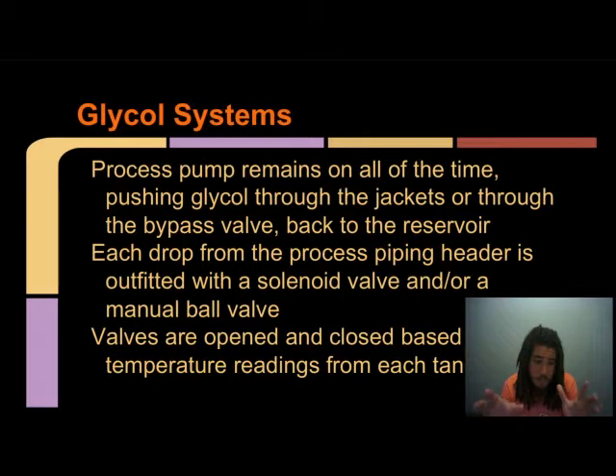So each drop from the process piping, so you have your main inlet header, where the glycol is pumping through via the process pump, always. From each of these, there are tanks underneath them, or above them, wherever it's situated. From the big trunk, your big header, you'll have drops from the header to the fermenter that carry the glycol from the header to the fermenter. Usually each of these drops in the process piping will have a solenoid valve and/or a manual ball valve installed. And the valves are opened and closed based on the temperature readings from each tank.